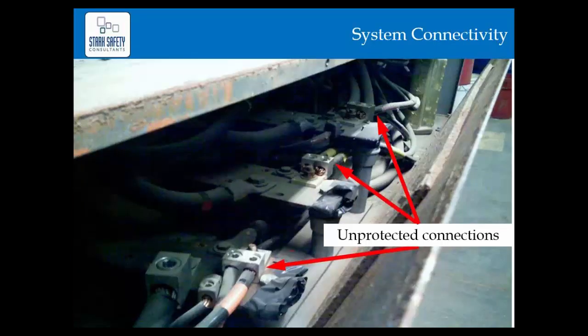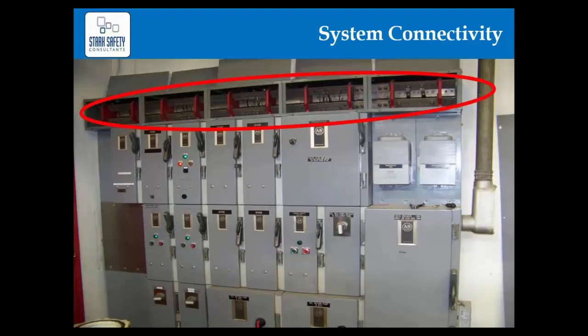Very common - here's another trough example of a similar application, and you can even see where they put electrical tape on the ends just because it was rubbing up against the cabinet and they didn't want a live conductive part exposed. You never know what you're going to get into, who was there last, what they did, or what their knowledge, skill, or qualifications were. So you always have to go in prepared for the worst, or prepared for unknowns, when you open things up.